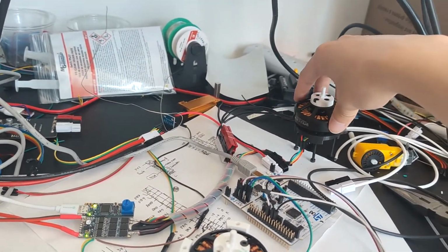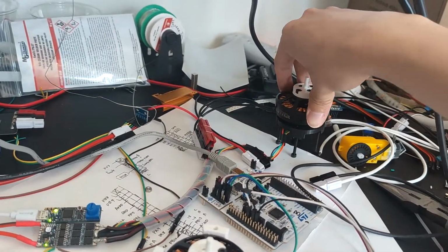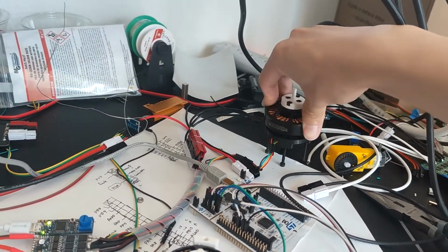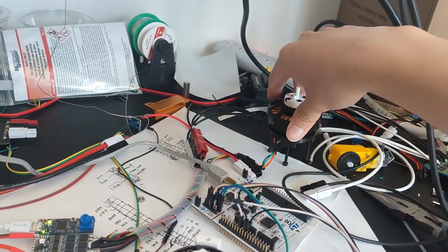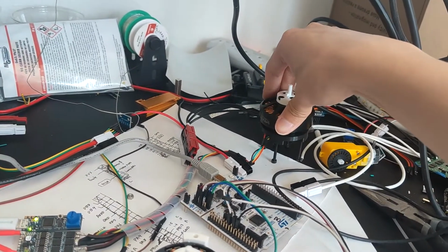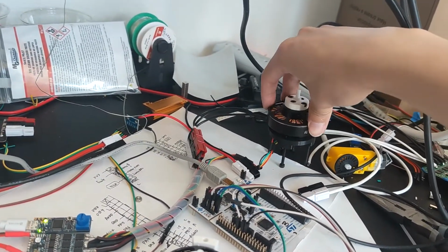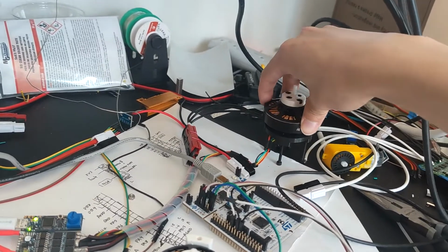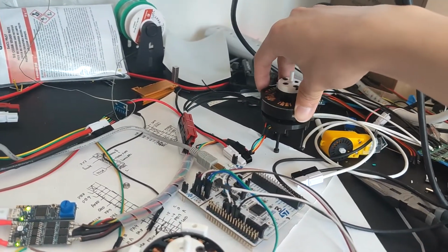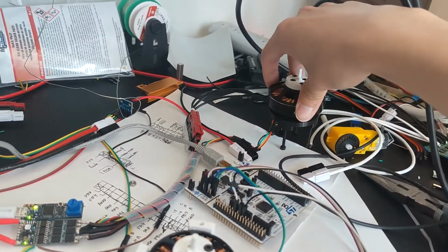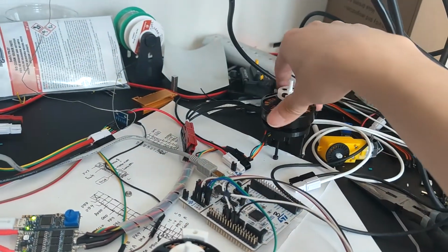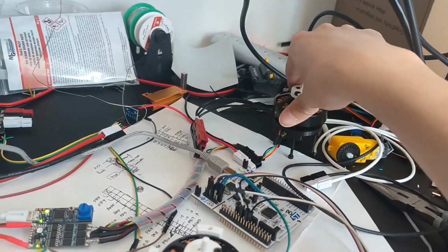So the motor in the position control loop will respond normally, it will try to go back to its original place, but then on a 3 Hertz cycle, there's a sudden torque.